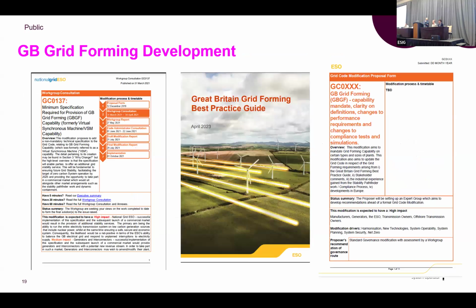To tackle these challenges, one thing we think is fairly important is looking at it in a very structured way: what does the system actually need in the future when more and more IBR connect? Some of the good services provided by synchronous machines are no longer there, like inertia and fault level support. If IBRs can behave like synchronous machines, maybe some of these problems can be resolved. That's what we started our work on grid forming development since 2013.